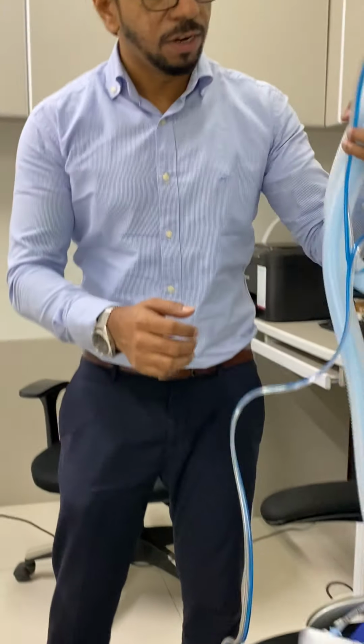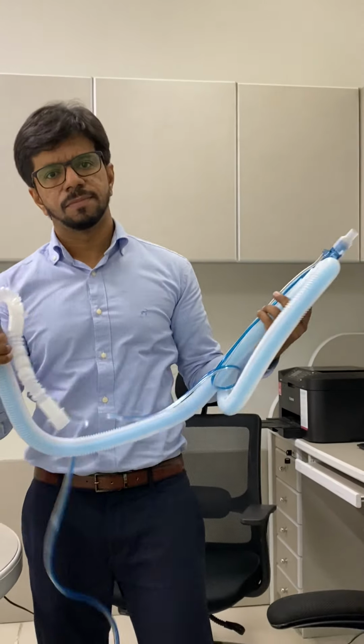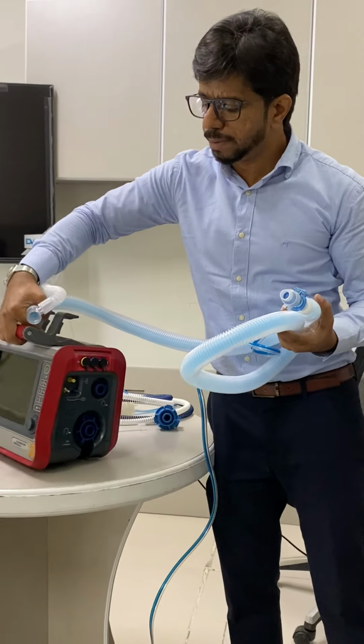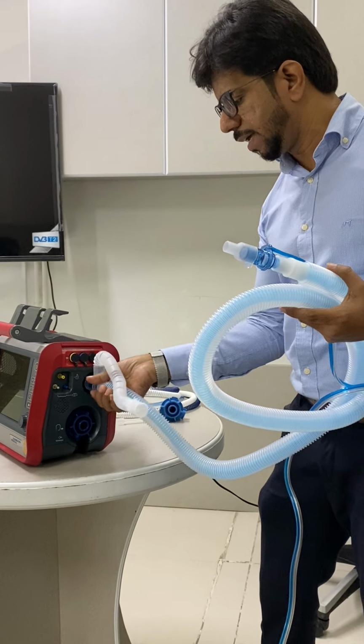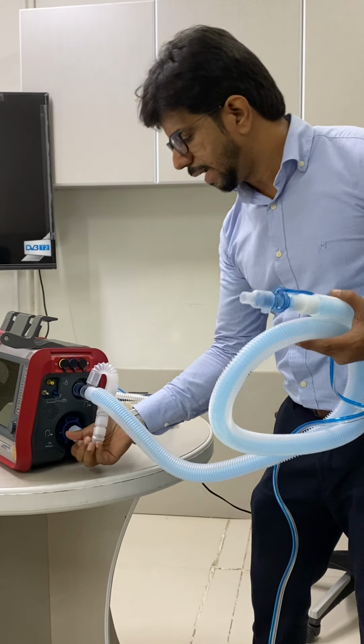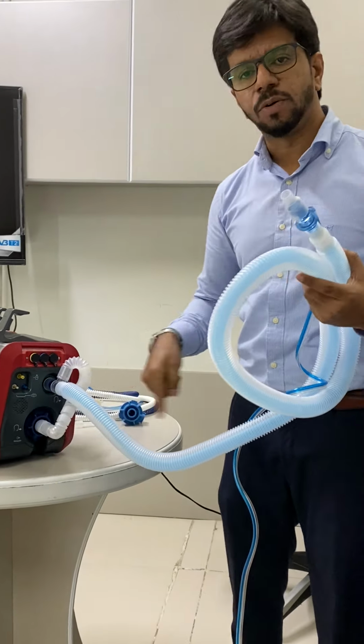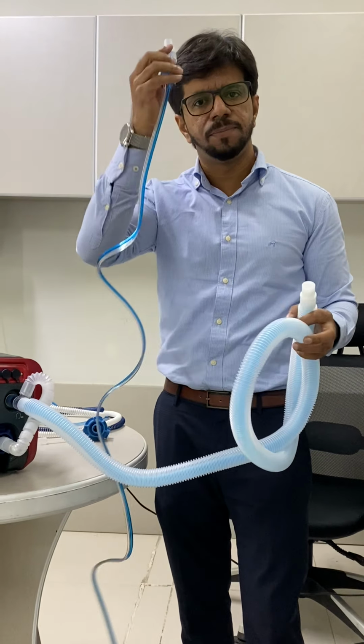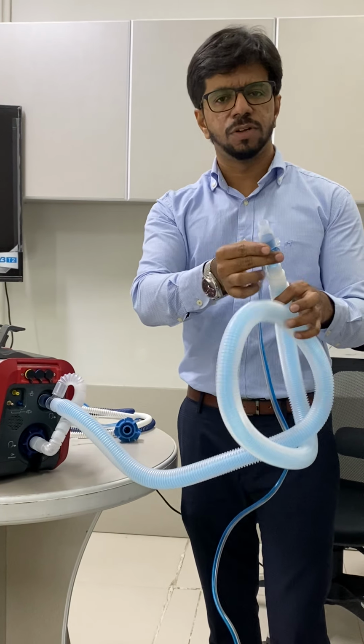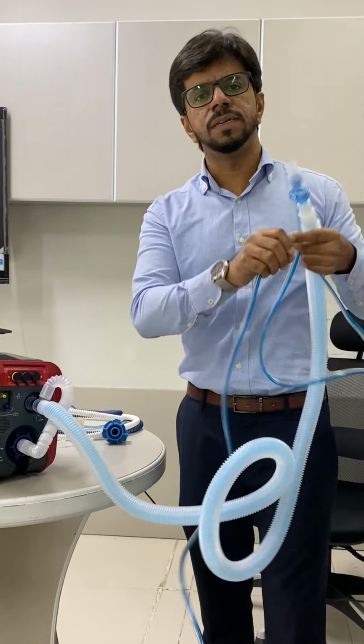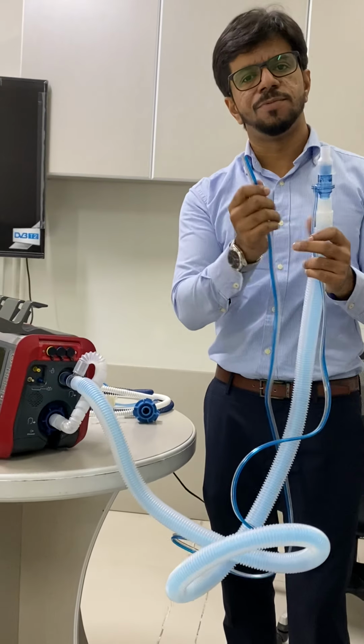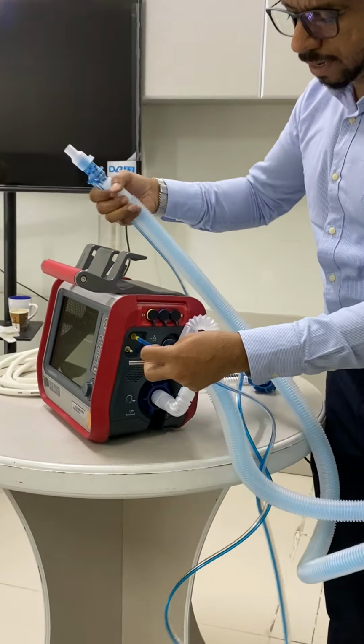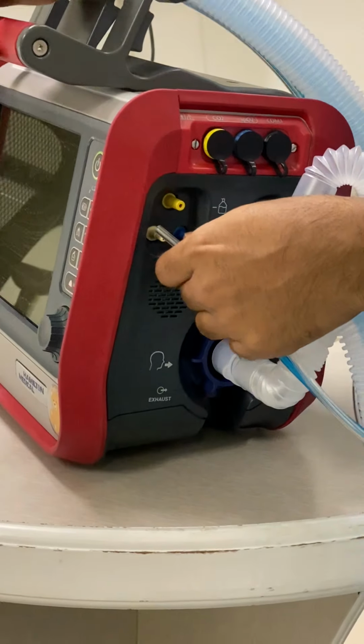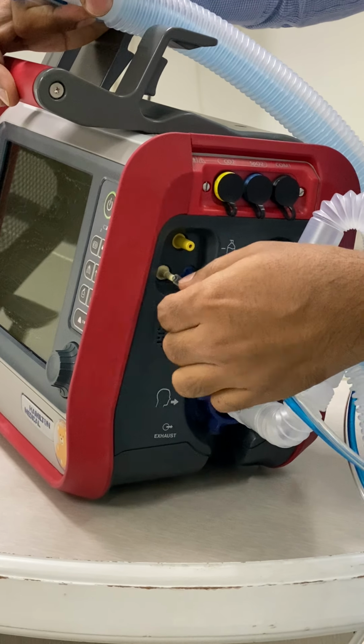You can use any double limb circuit. When you're connecting the double limb circuit, you connect the inspiratory line and the exhalation line. This is the coaxial circuit, and you have the proximal flow sensor. You connect it to the Y, and it is color coded, blue and clear. So you can connect the flow sensor tubing accordingly, blue and the clear one.